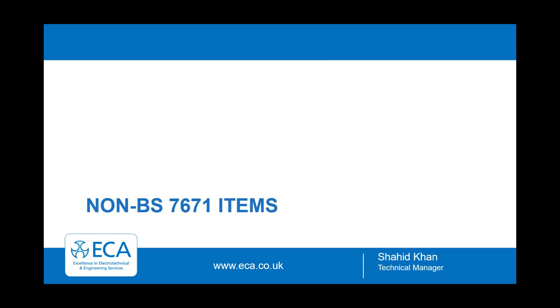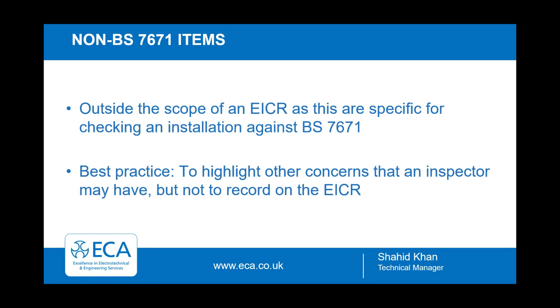Non-BS 7671 items. This is another common question that people ask: what do you do with non-7671 items? So, for example, while conducting a periodic inspection, you notice an issue with the emergency lighting provision of a building. This defect actually falls out of the scope of 7671, so shouldn't really appear as a defect on an EICR, as the emergency lighting provision is covered by a different standard entirely, 5266. It is, however, best practice to bring issues such as this to the attention of your client to aid in achieving a much safer installation overall.